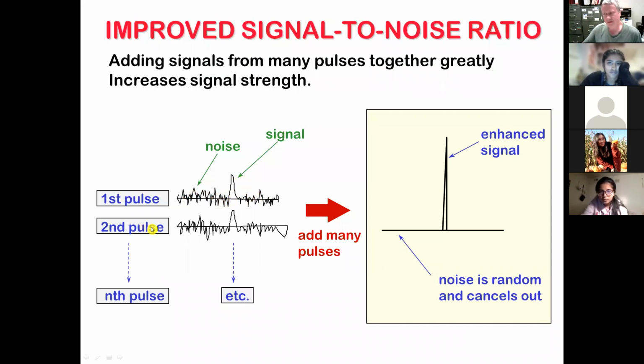Then I do it again. Oh no, poor signal. What if I do this 20,000 times? You just do it 20,000 times. Beautiful. Now I have a beautiful spectrum. It's nice that I can repeat this 20,000 times and convert a really garbagey looking spectrum into a very beautiful spectrum. That's why we use Fourier transform NMR, because we can do multiple acquisitions, average them out, and get a beautiful baseline spectrum.